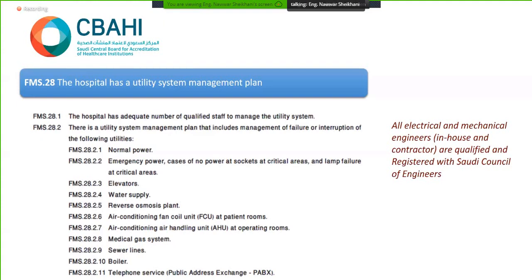28.2, utility system management plan that includes management of failure or interruption, from normal power to emergency power, elevators, boiler, fire alarm, etc. We should have a plan B or alternative solution for each system, from 1 to 13, with the action and procedure detailed. If you have forms for that, attach them with the plan and number the pages in accordance with the policy, so they become part of the plan.